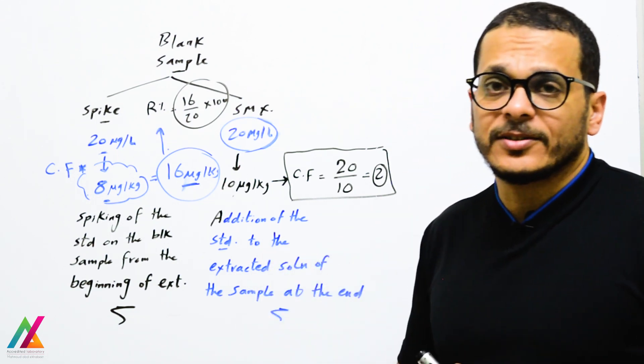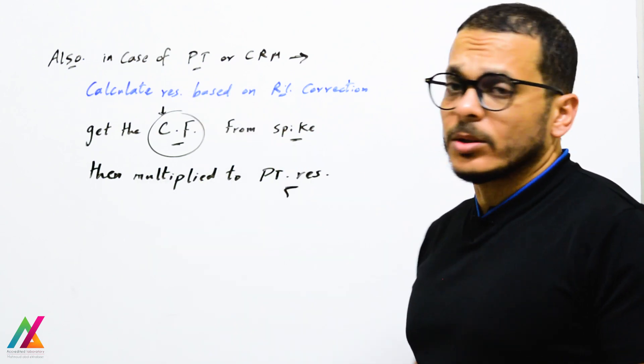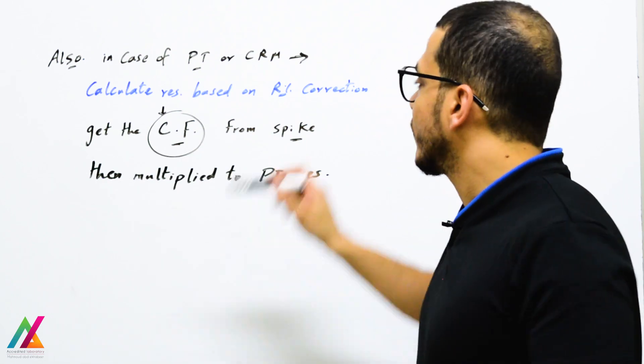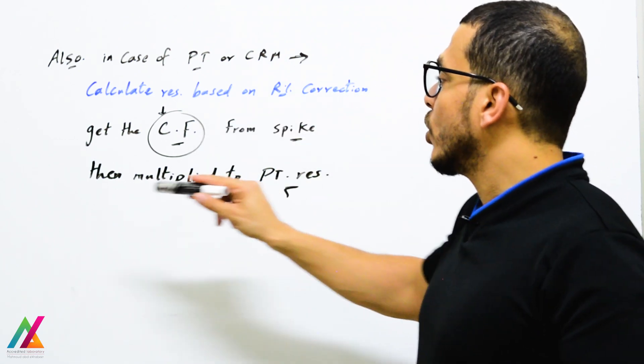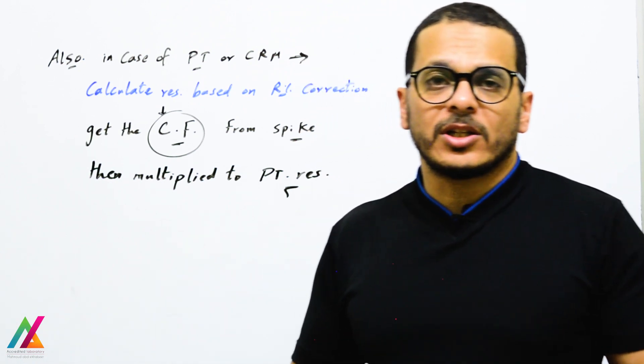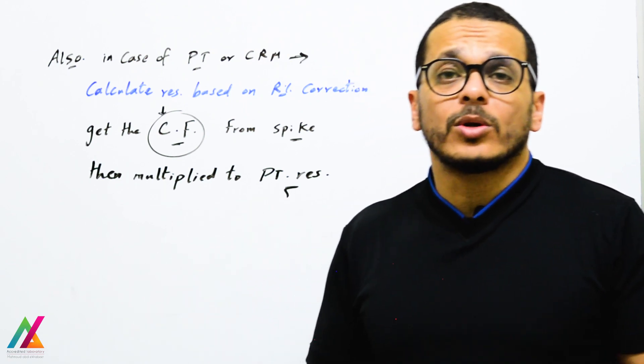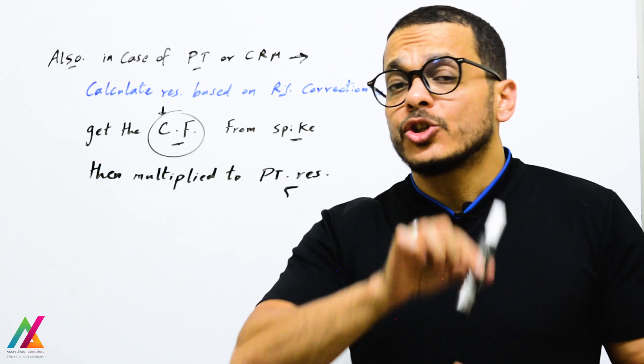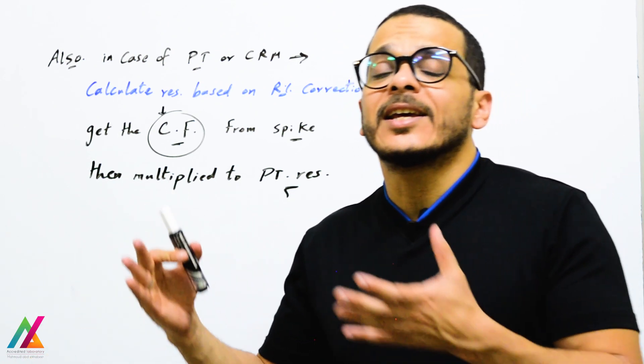For PT or CRM samples, if the report says 'calculate result based on recovery correction,' derive the correction factor from the spike sample itself, then multiply it to the PT or CRM result to get the real concentration. This differs by method, lab, and equipment, but ultimately all correction factors — dilution factors, recovery correction factors, or reference values — shall be updated and implemented in the equipment or software to obtain the real result.